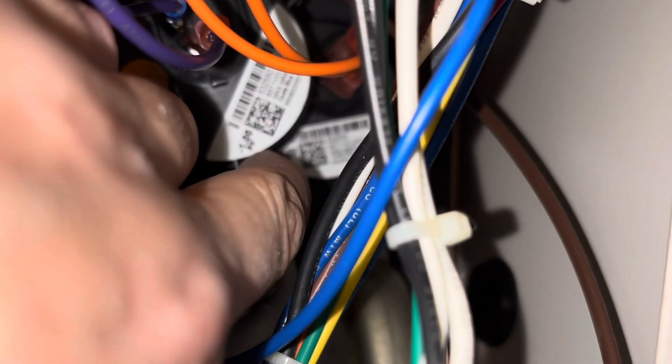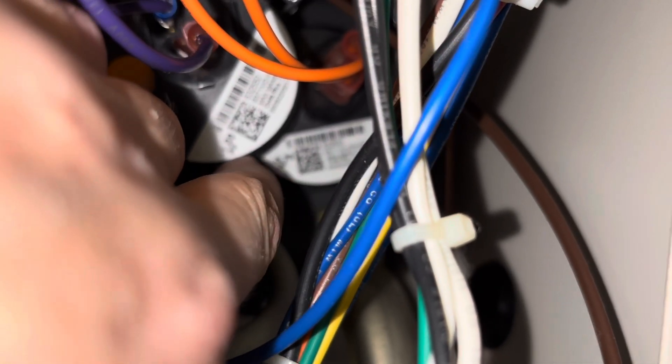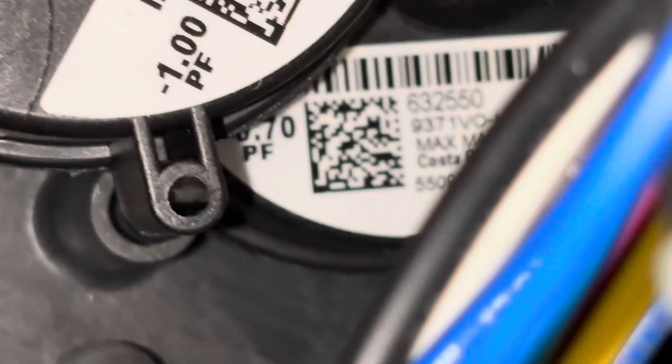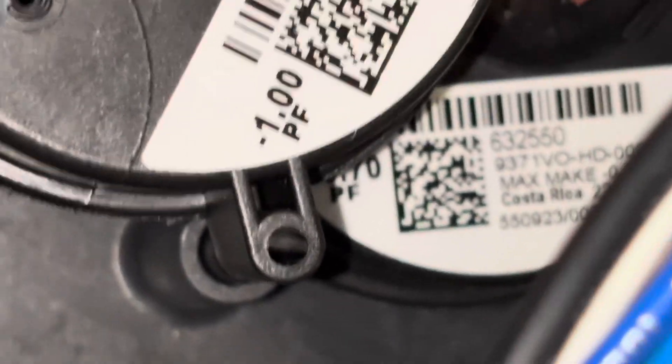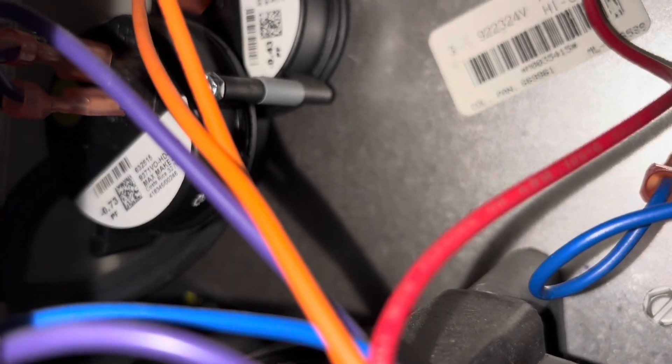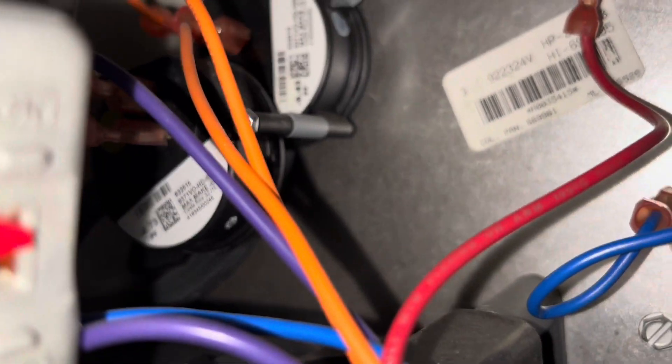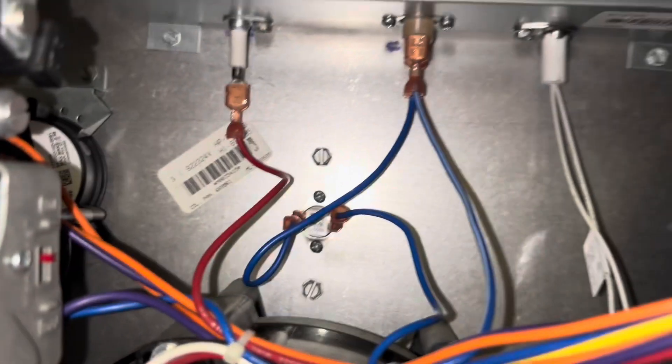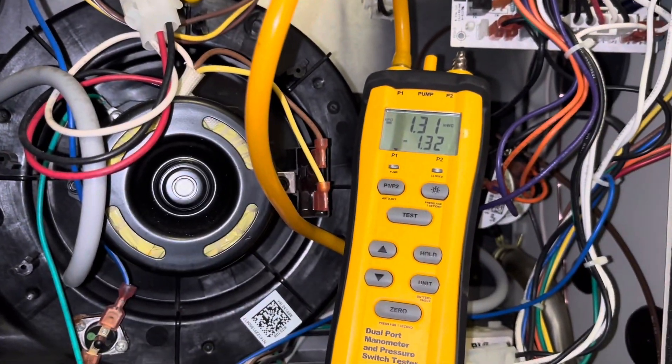And something also weird about these pressure switches is, if you jump one out, it actually won't go into an error when it goes to start back up again. As long as one switch opens or closes, it's fine. I don't know, it's a weird furnace, it's a weird furnace setup. So there's my other two pressure switches up there also. The purple wired ones, one on top, one on bottom, are for second stage. The orange wired ones are for first stage.